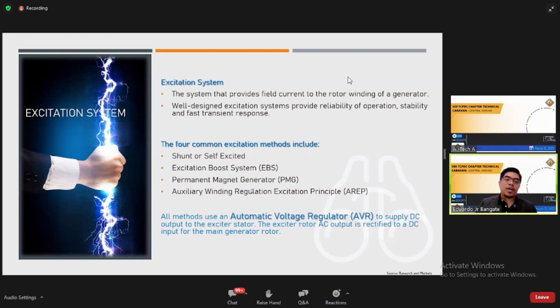We have four common types of excitation methods nowadays. We have the shunt or self-excited, the excitation boost system or EBS, the permanent magnet generator, which is very common, and the auxiliary winding regulation excitation principles or the AREP. However, all these four excitation methods use an automatic voltage regulator or AVR to supply DC output to the exciter stator. The exciter rotor AC output is rectified to a DC input for the main generator rotor.